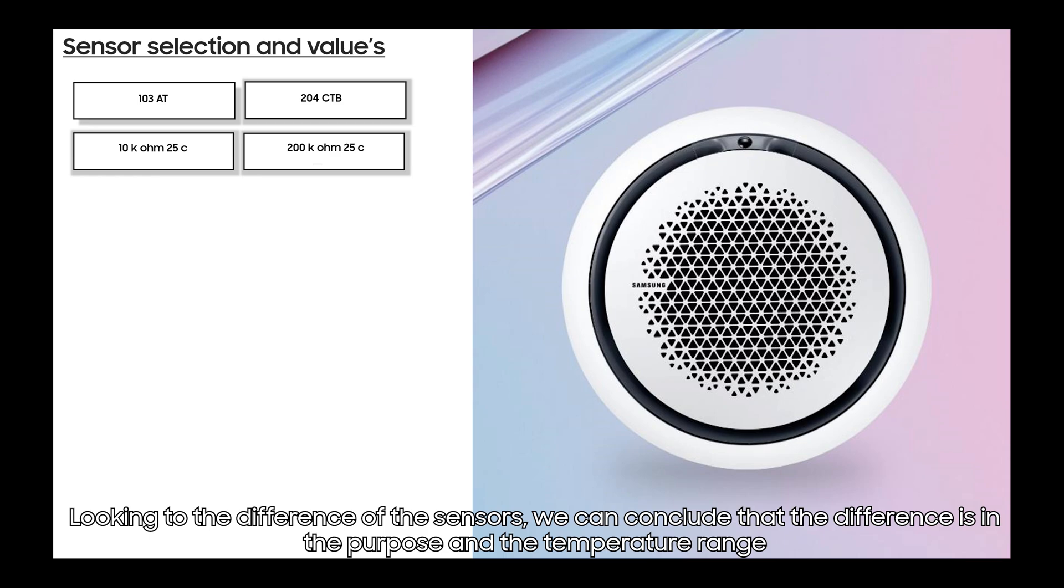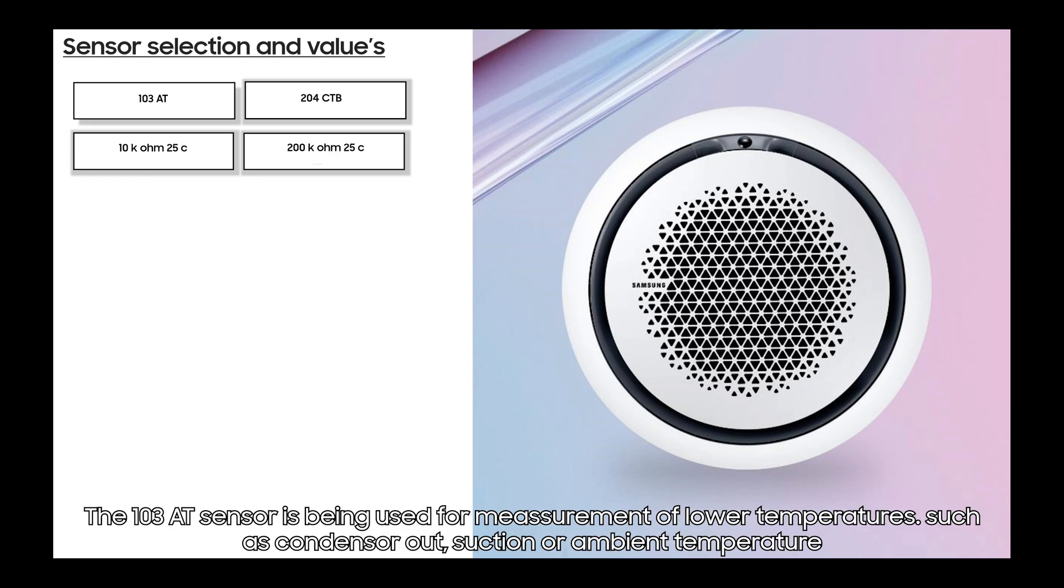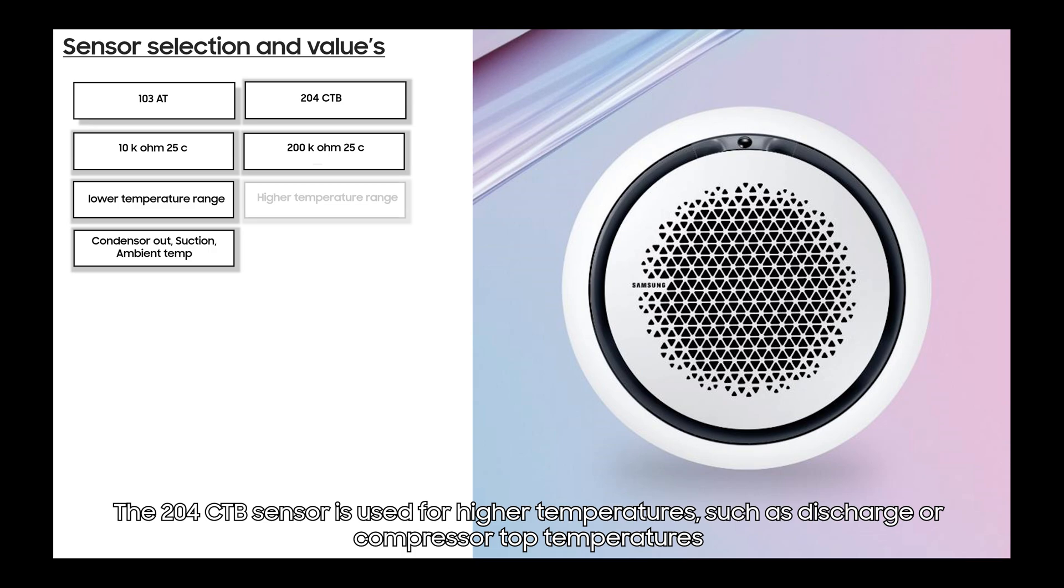The 103 AT sensor is used for measurement of lower temperatures such as condenser out, suction, or ambient temperature. The 204 CTB sensor is used for measurement of higher temperatures such as discharge or compressor top temperatures.